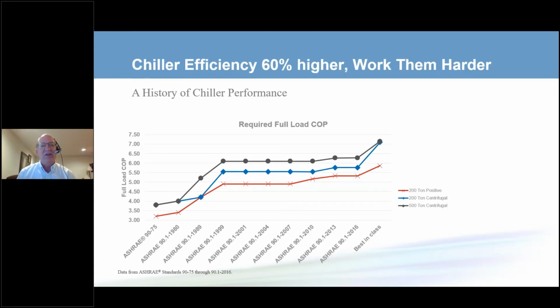But as engineers, we now need to ask the question, why? What changed? What's changed since about 1975, so over about the last 45 years, is the efficiency of chillers. This is a graphic of the efficiency of chillers, the minimum requirements per ASHRAE Standard 90.1 over the years, and then what the best technology can deliver today.